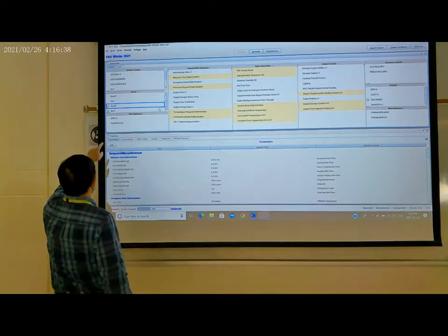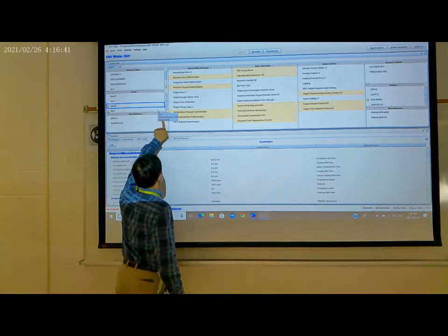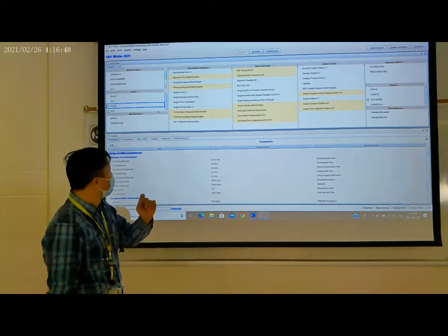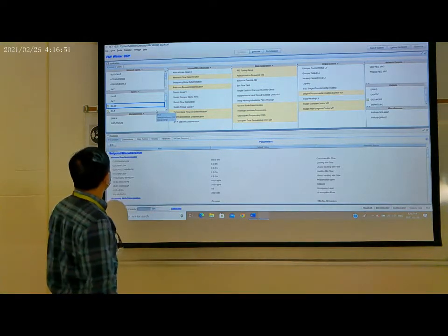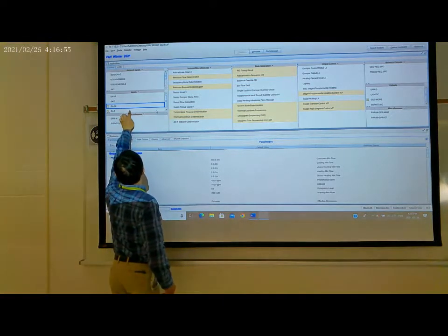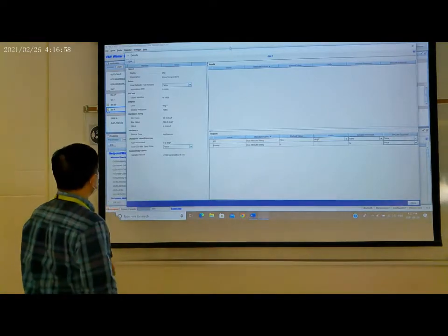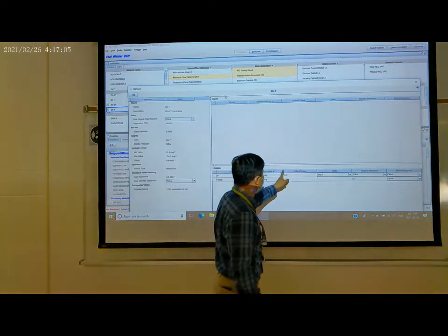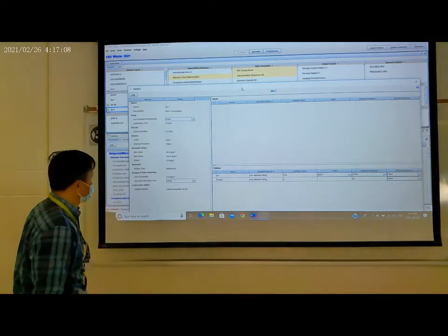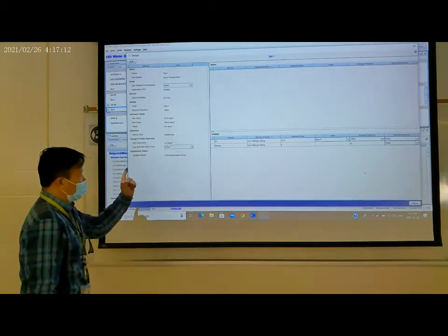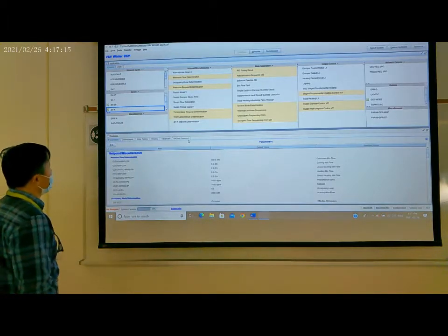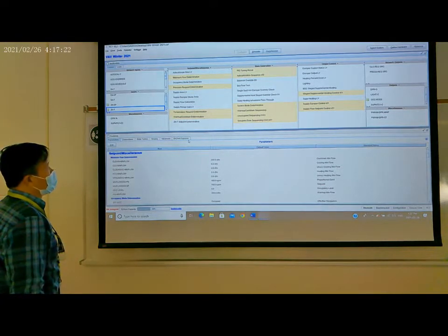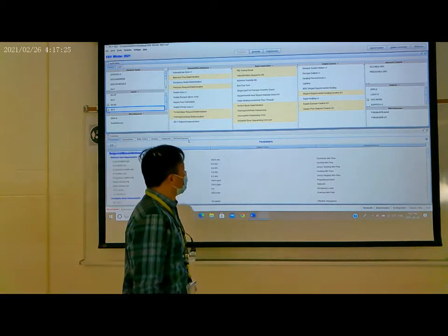And then we see the zone temperature input. Same thing, it's SA bus, which means the thermostat sends the temperature to the controller. So this is okay. And then we double click to see here, the default is 72, so it's fine. And then close. Now we complete the input signal setting.